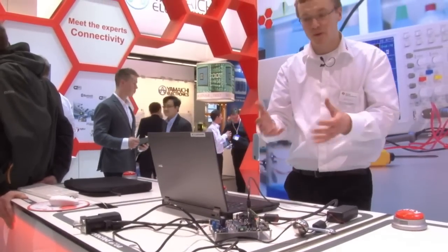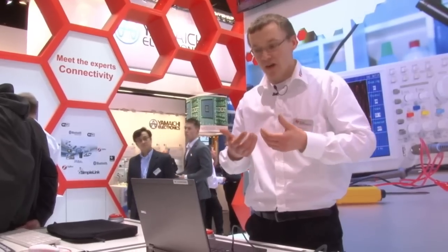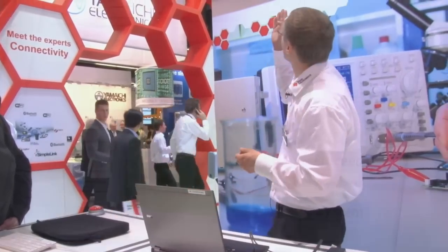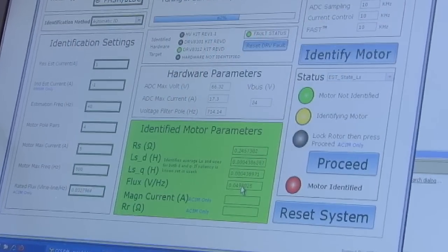Now I start the software algorithm that estimates the values I need for the software sensor to give you a proper angle. Now it's running for two minutes and then I have the motor parameters. As you see on the screen, the RS and the LD and Q and the flux values.